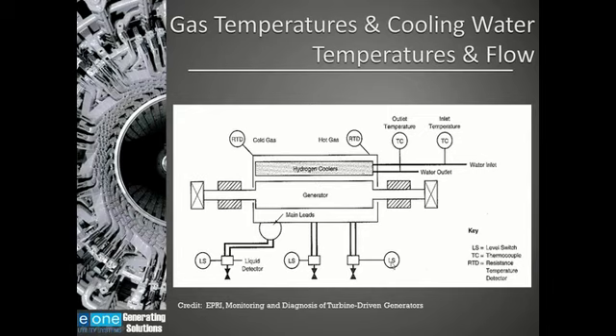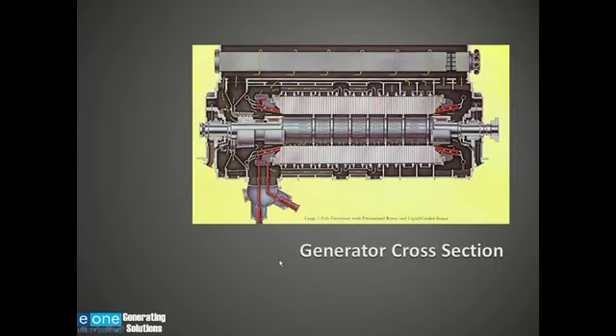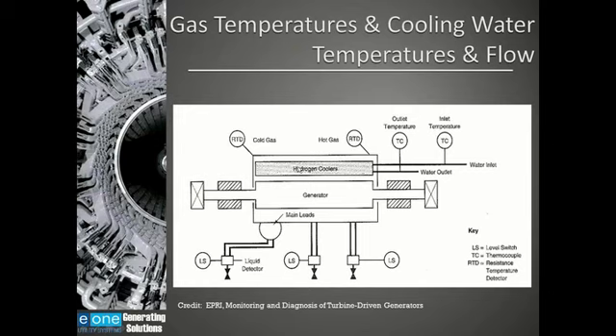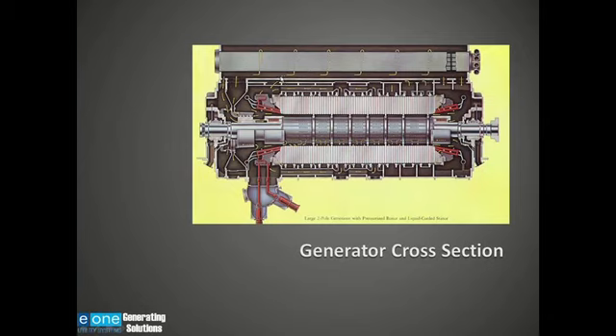And then you'll notice down here I've got some liquid level detectors. These are monitoring for oil or water that could be in the generator. These are switches. I just wanted to again show the hydrogen cooler that is shown here. This part right here is the hydrogen cooler. And again, we have the hot gas coming into the cooler, cold gas comes out of the cooler, and my inlet and outlet water are coming over here. And again, by measuring those, we can tell the effectiveness of this cooler and how well we are removing heat.